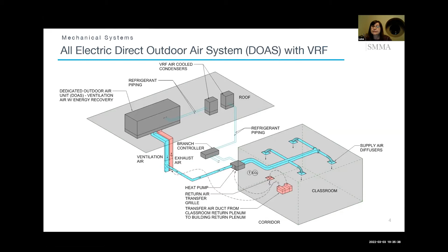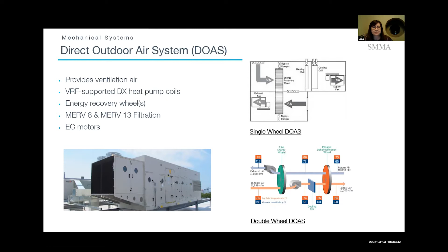One of the main components of this system is a direct outdoor air system. Among the many components that make up this unit, I just want to start by talking about what this unit does. These units provide ventilation to the building, fresh air. As I mentioned, the coils in these units will be heat pump style, DX expansion. Each unit will have at least one energy recovery wheel, and sometimes it could be two. The unit will have a multi-step filtration system, and the motors used in the unit will be high efficiency EC motors. At the bottom of the page, you see how the system looks. On the roof, on the right-hand side, you can see the composition of the system, depending on the requirements by the spaces. Next, please.